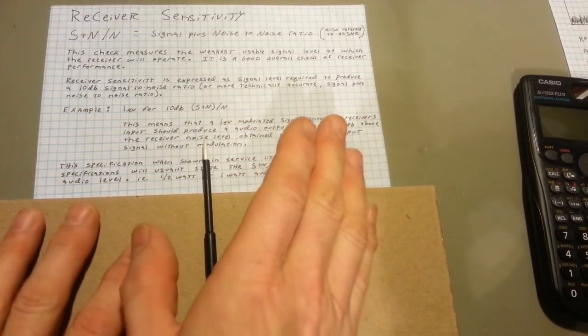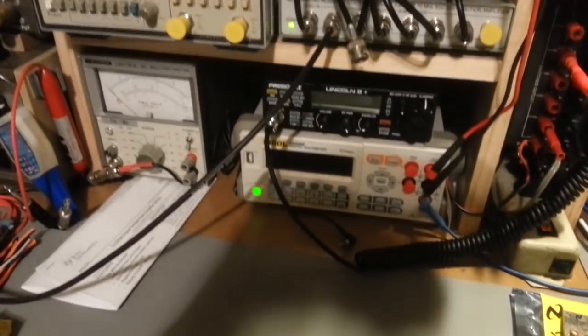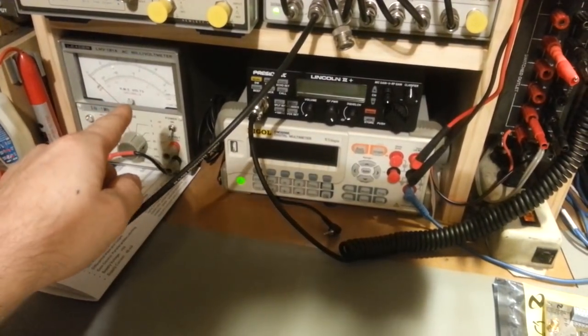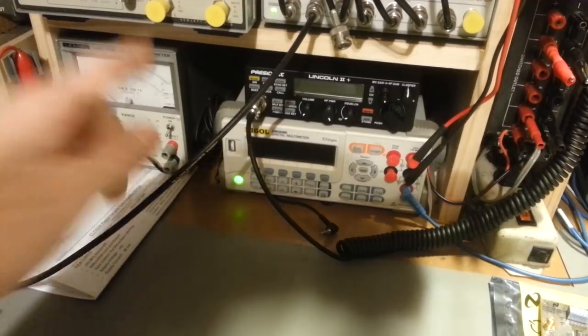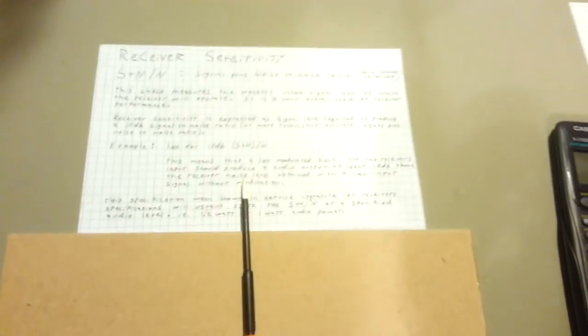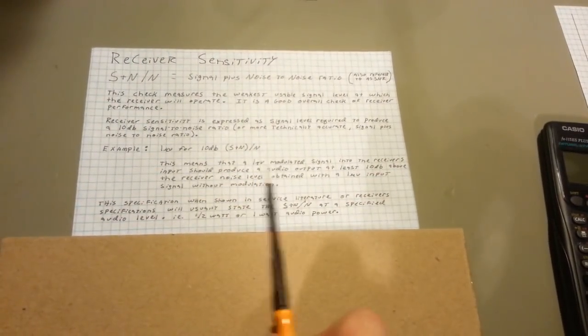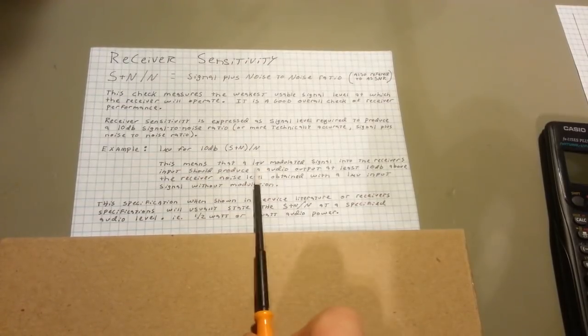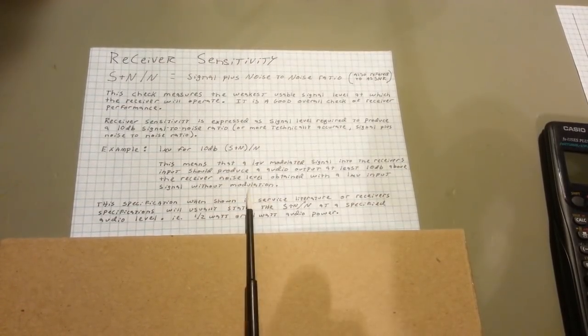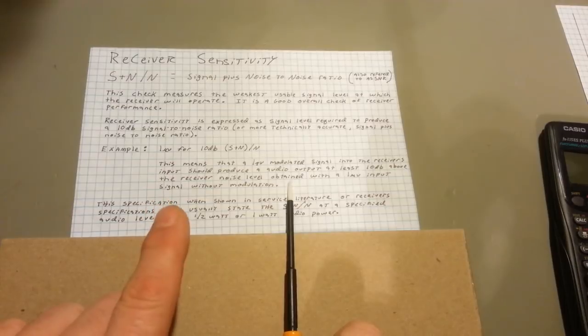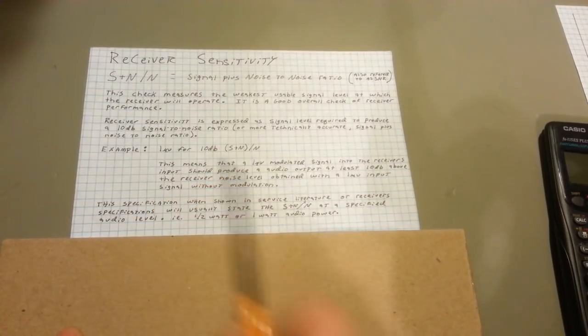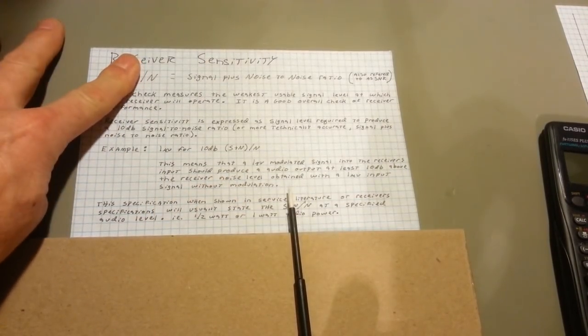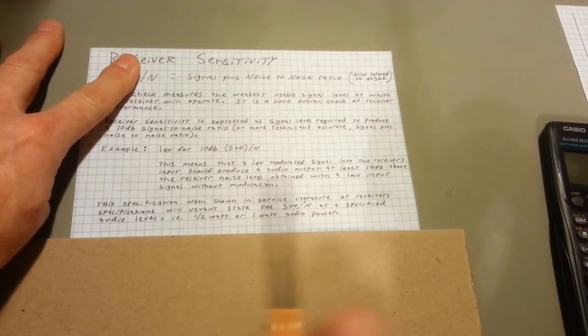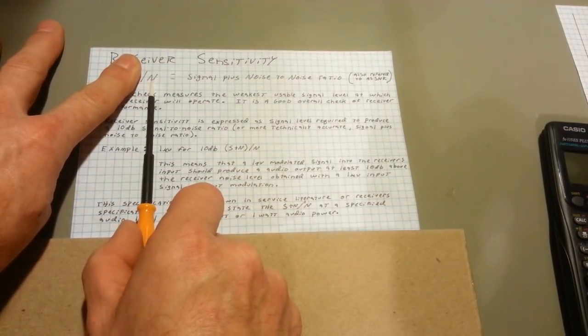And usually what I do, it makes it easier, is you would put the input signal so the needle rests right on 0. And then all you do is, because remember, the other half of that measurement is with a modulated signal. So without modulation, that's your noise. That's your N measurement. Okay, so that's actually what you're taking when you inject a 1 microvolt signal into the radio. You're taking that measurement right there.